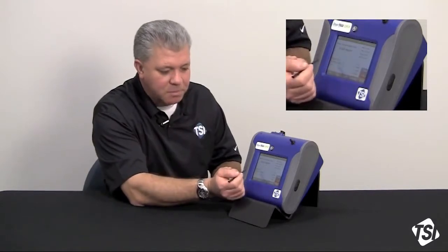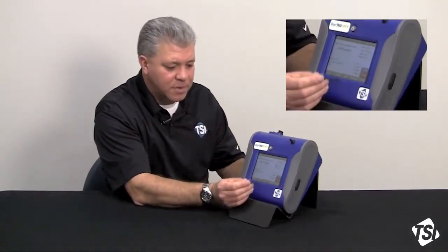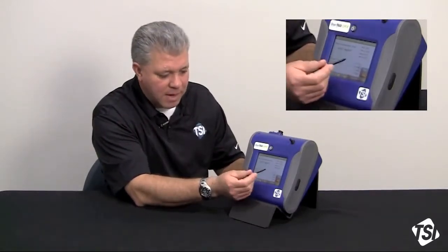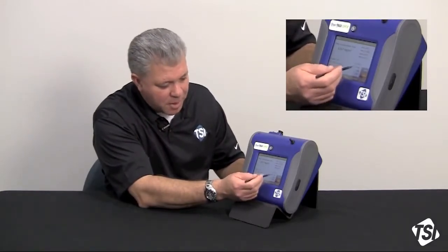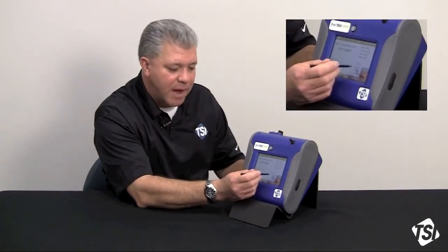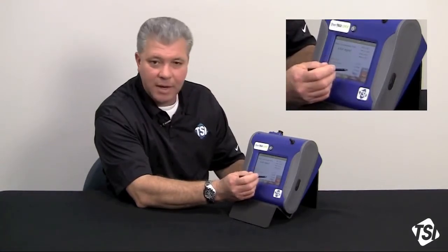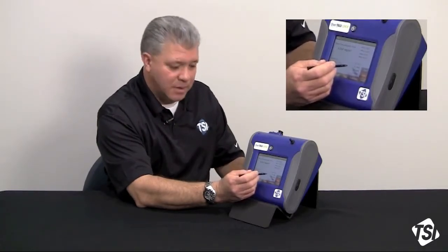Again, you've got your stats buttons. And then over here, you have some indicators that are relative to the instrument's performance right now. We don't have a STEL alarm set. We have a pump, a laser, and a flow. So if you ever have an error with any of these green radial buttons, they'll actually turn to red in color, indicating that there may be an issue with the instrument.